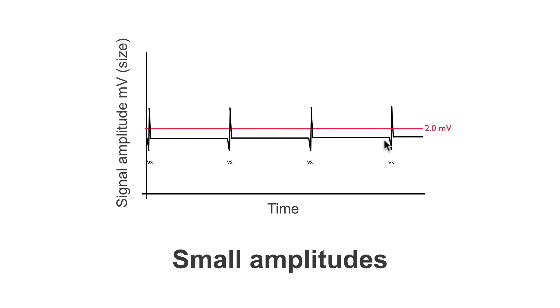Again, we can see that the amplitude size has also improved. Before we were just marginally over 2 millivolts, and now we can see these ventricular signals are much greater than the 2 millivolts that the ventricular sensitivity is set to. This will put your mind at rest that the pacemaker will continue to function normally.